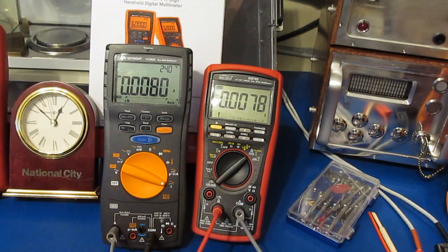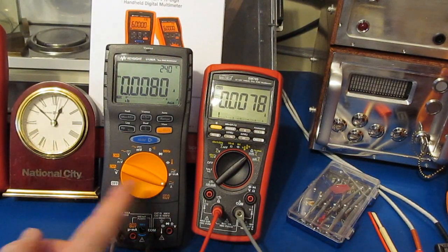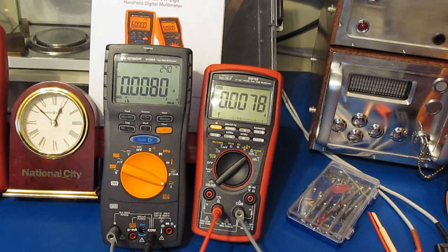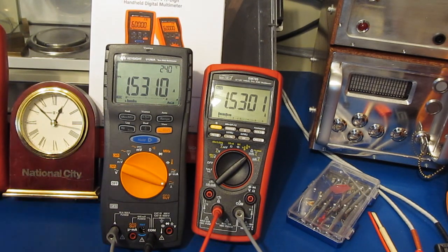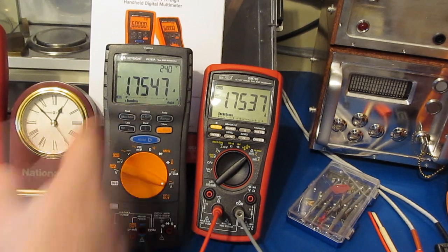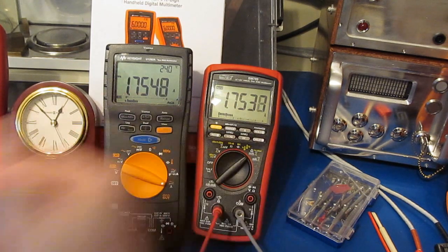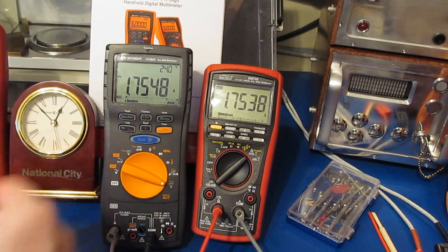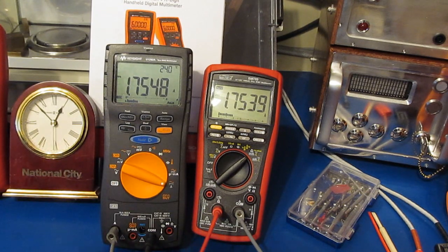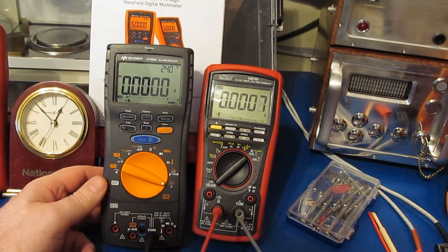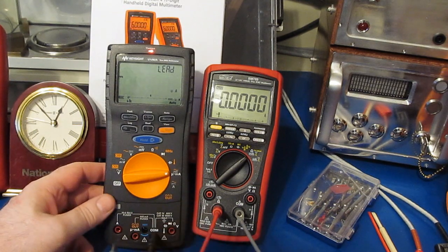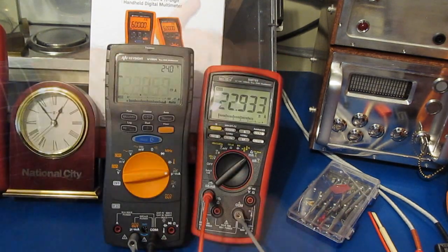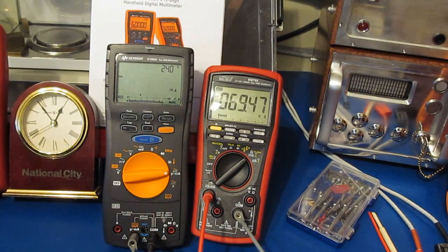So these two meters are now in series, and then I'll apply a little bit of current to the input. Alright, and that's pretty much the limit of this power supply. So you can see 1.75 versus 1.75. So it doesn't appear that we've damaged the amp input. Let's remove our test lead and go to microamps, and we'll do the same thing with our little Brymen. And we'll turn up the current again a little bit.